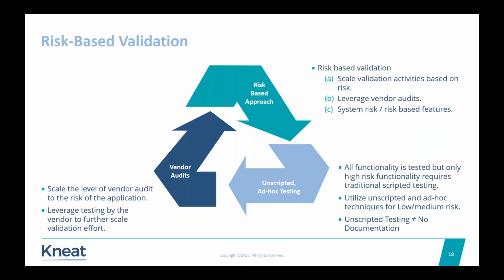So you utilize unscripted and ad hoc techniques for low or medium risk. And the last part I can't emphasize enough is unscripted testing does not equal no documentation. You cannot identify something as a low risk feature and say, we didn't bother testing it. Use the ad hoc approach, let the tester write in how they tested it.